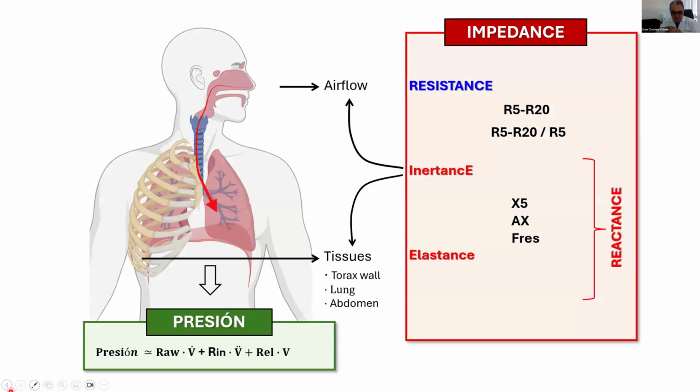Oscillometry allows measurement of the respiratory system impedance. Physiologically, this impedance quantifies how easily air moves in and out of the respiratory system. It is composed of respiratory resistance, related to the resistive properties of the respiratory system, and reactance, linked to the elastic and inertial properties of the system. Oscillometry permits us to measure the small airways and therefore small airway dysfunction.